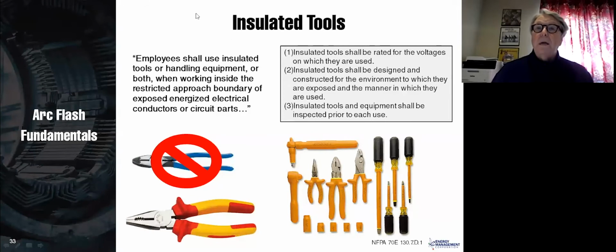So it happened to me, it could happen to you. Now, if you have electricians and they don't operate on energized equipment very often, if the OSHA guy had pulled out this set of pliers and said, "Do you ever work energized?" and the electricians had said, "Yes, we work energized, but not with these tools. Anytime we work energized, we have a special set of insulated tools that we work with," that would have been fine. But it is an OSHA requirement that you use insulated tools. And so, word to the wise, my pocket's $50,000 thinner because of that, and it could happen to you.